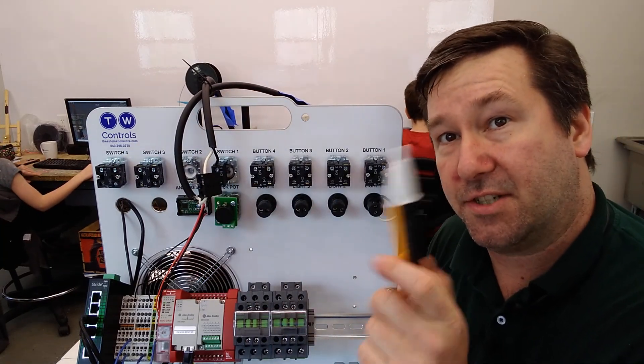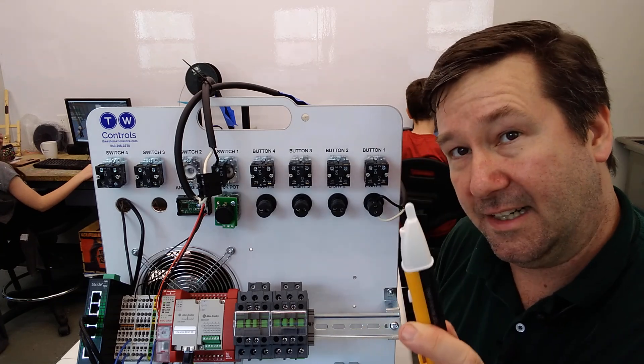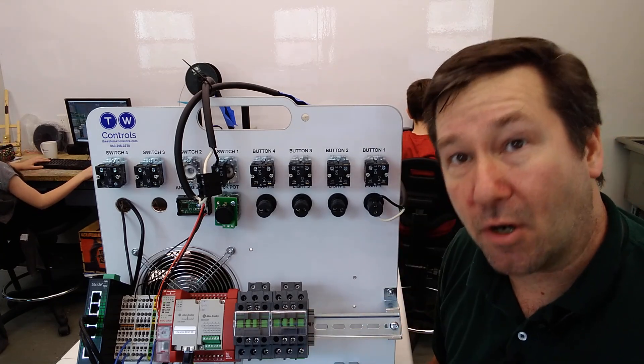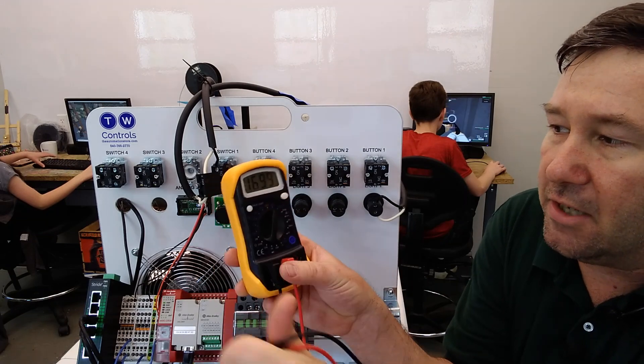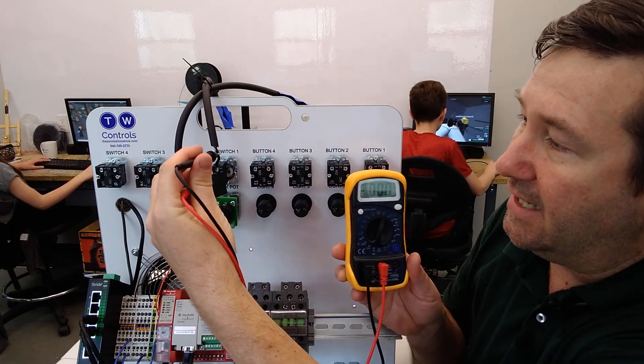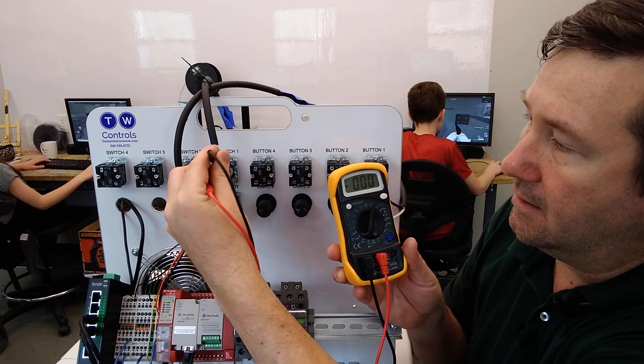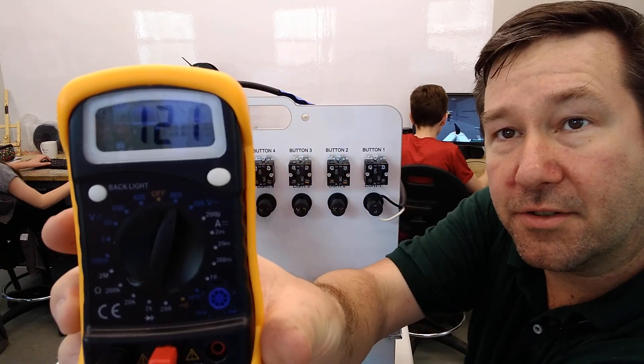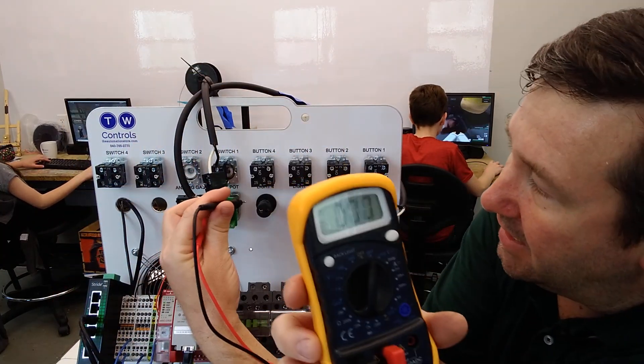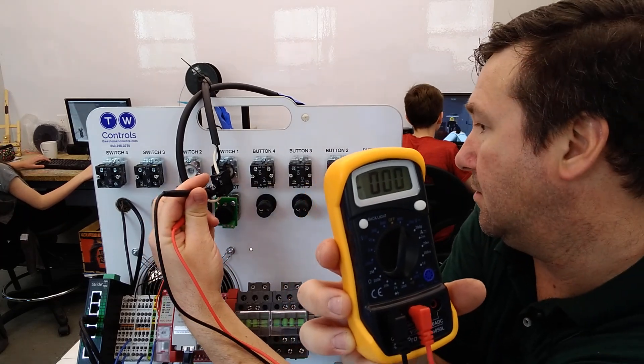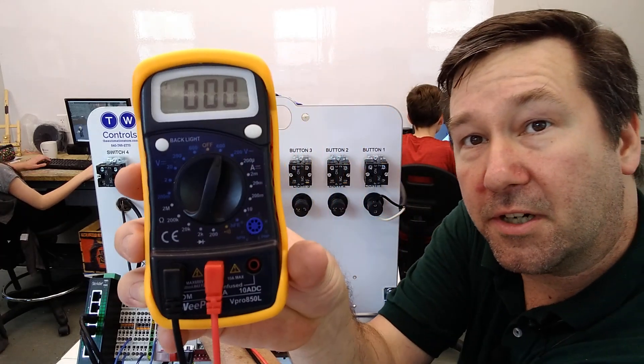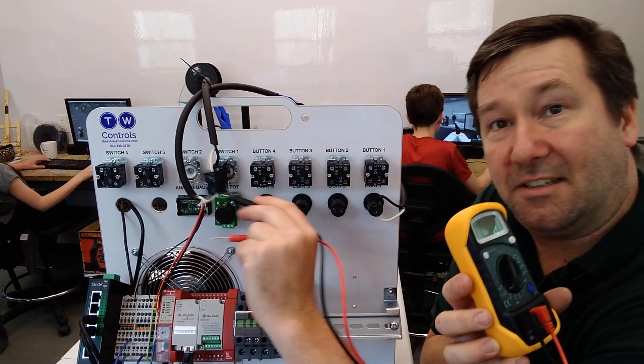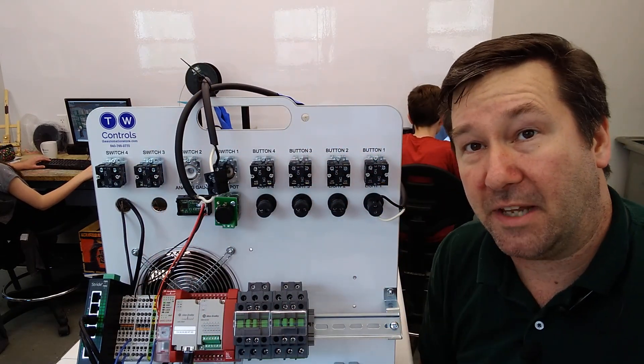But this checks just for voltage present. This doesn't actually check that we have current load. So if we take our meter and put it on AC voltage, if we test the top of this, then we're going to have 120 volt. But if we test the bottom of this, then we're going to have zero volt because I've taken this contact loose to simulate that break that we had.